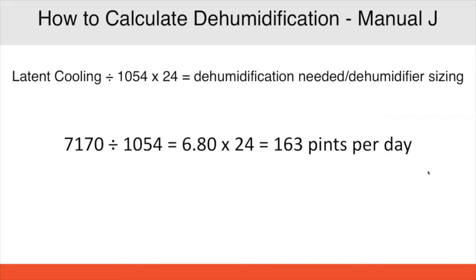So are we going to count on our AC system to handle that? Or are we going to pick a dehumidifier that will handle all that load, or just supplement the AC when it isn't running? Those are decisions that we're going to have to make. And I will tell you that working more and more with builders, and definitely more of the forward-thinking HVAC contractors and mechanical engineers, they are looking at addressing all that latent load with a dehumidifier and not leaving it up to the homeowner to run air conditioning in order to always be able to maintain that 50 to 55% RH in the home.